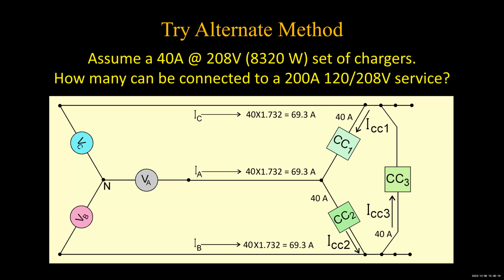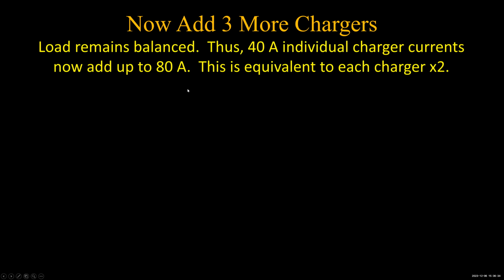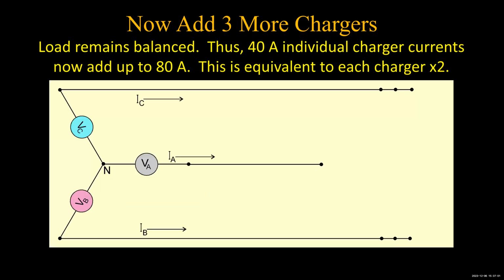336. Just want to check here. So here's the secret. You've got to multiply this by 1.732, not by 2. So if we add 3 more chargers to the system, then the load is still balanced, okay? But the individual chargers are still 40 amps, or in other words, you've got 80 amps between line 1 and line 2, or phase A and phase B, and 80 amps B to C, and 80 amps C to A. But when you convert that to line currents, it's going to be 80 times the square root of 3, as we'll see.